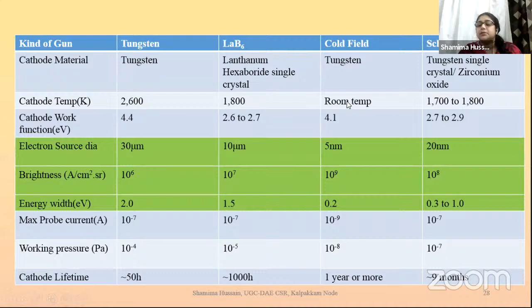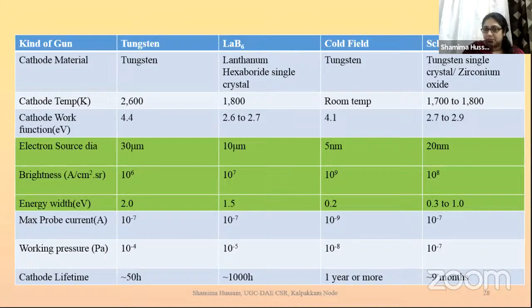Now, look at the lifetime that I was mentioning: 50 hours for tungsten, which is close to 3 days. Lanthanum hexaboride is almost 1,000 hours. It's higher, but not that high. Schottky had 9 months, because in between there was downtime when we were cleaning the diode surface. And for the FEG, 1 year or more is mentioned. I myself have personally used it for more than 2 years. So it's quite sturdy that way.